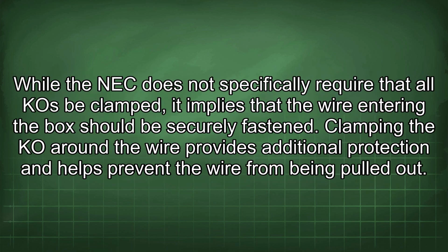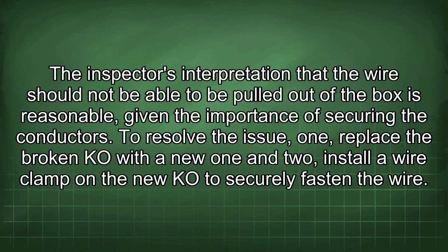While the NEC does not specifically require that all KOs be clamped, it implies that the wire entering the box should be securely fastened. Clamping the KO around the wire provides additional protection and helps prevent the wire from being pulled out. The inspector's interpretation that the wire should not be able to be pulled out of the box is reasonable, given the importance of securing the conductors.